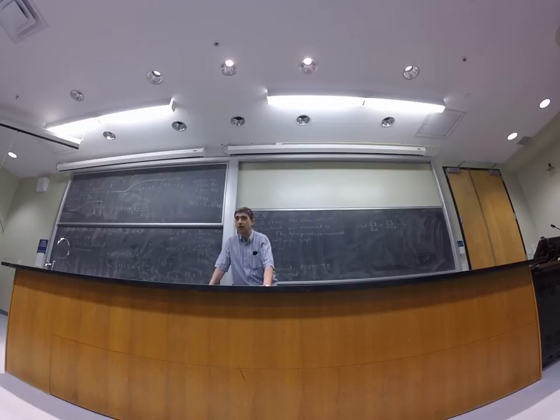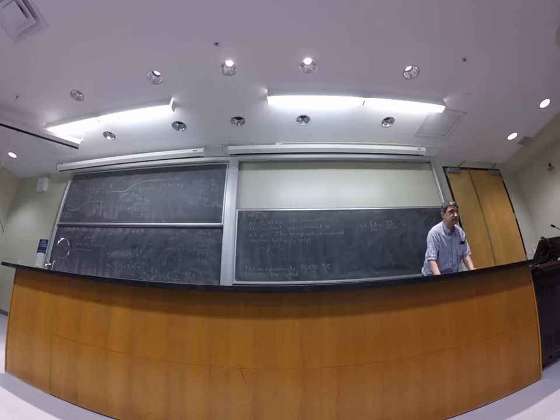If you mess up that sign, I may give you 0 partial credit. Always make the mental check. If the input and measurement are moving in the same direction, it should be positive. If they move in opposite directions, it should be negative. So you calculate something, stop, check. What do I have here? Flow rate of coolant and temperature measurement. If I increase flow rate of coolant, what happens to temperature measurement? Goes down. Opposite direction, so it should be minus.